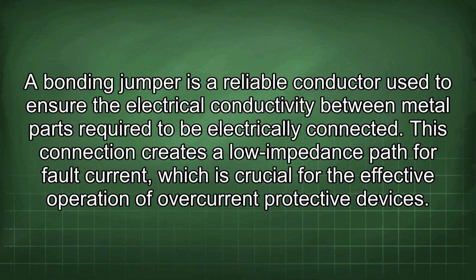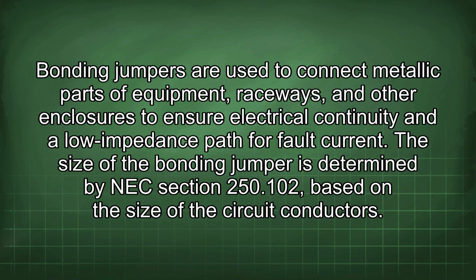A bonding jumper is a reliable conductor used to ensure the electrical conductivity between metal parts required to be electrically connected. This connection creates a low impedance path for fault current, which is crucial for the effective operation of overcurrent protective devices. Bonding jumpers are used to connect metallic parts of equipment, raceways, and other enclosures to ensure electrical continuity and a low impedance path for fault current. The size of the bonding jumper is determined by NEC section 250.102, based on the size of the circuit conductors.